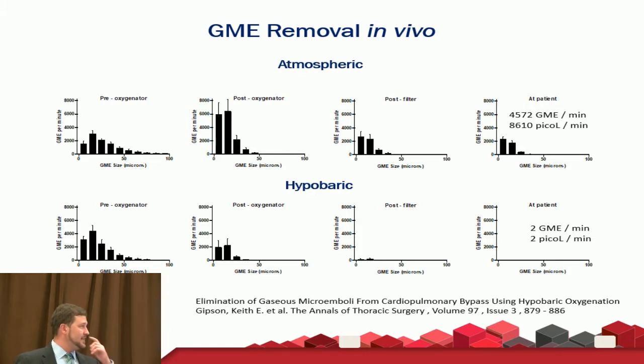This is Gipson. He did an in vitro study as well as pigs in vivo. They put them on bypass and ran them for 4 hours, measuring with EDAC and Doppler bubbles throughout the entire circuit. Pre-oxygenator was pretty consistent—they were injecting air to get a constant. Post-oxygenator, they wanted to see what happened; you can see there's still some air. But what's unique is that even post-filter, and then at the cannulation site, there was almost no air left in the system.